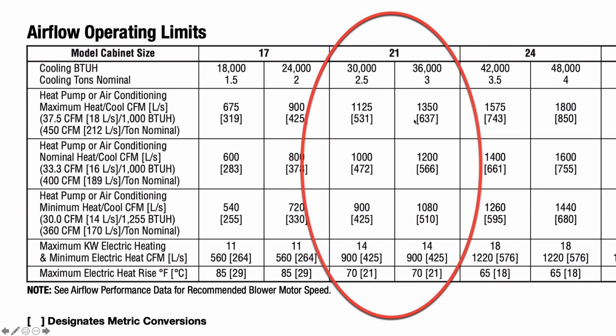So that cabinet referenced in my RBHP 21 can be either a 2.5 ton system or a 3 ton system. If it's a 2.5 ton, I'm looking for nominal heat and cooling CFMs, where nominal means that's perfect. I'm looking for 1,000 CFMs. If it's a 3 ton system, we're looking for 1,200 CFMs. Minimum would be 900 and 1080, but I don't want to deal with minimum. I always want to deal with nominal because systems do not get better with age.